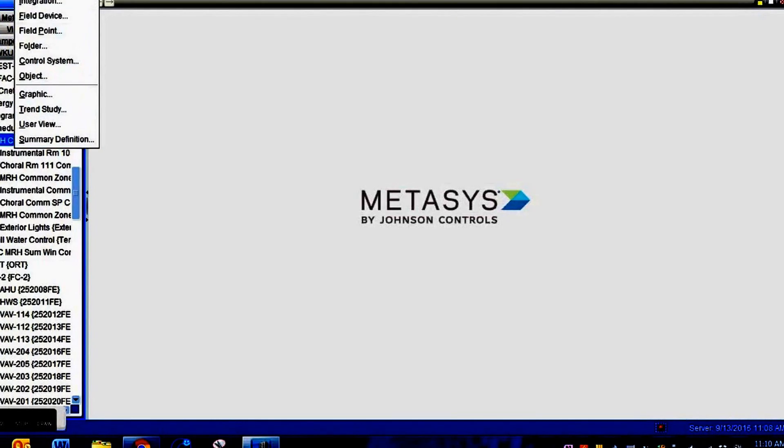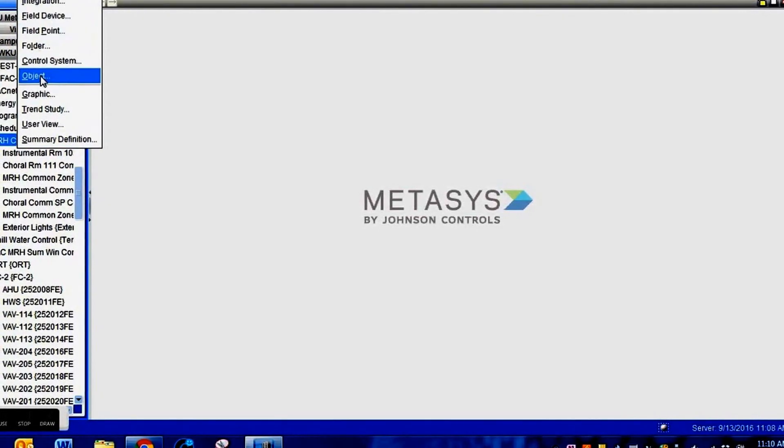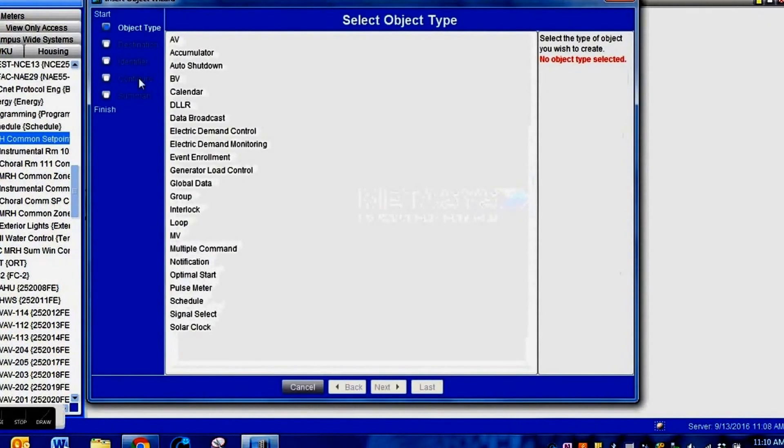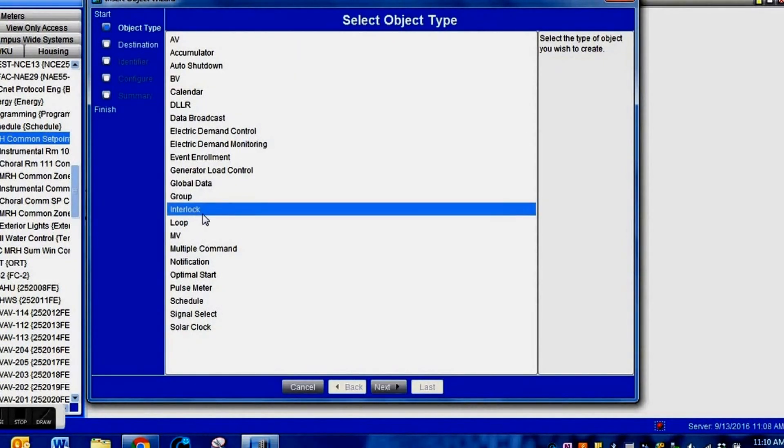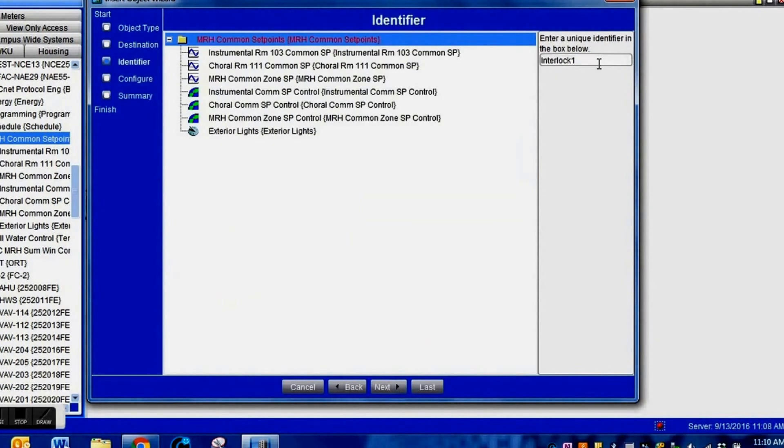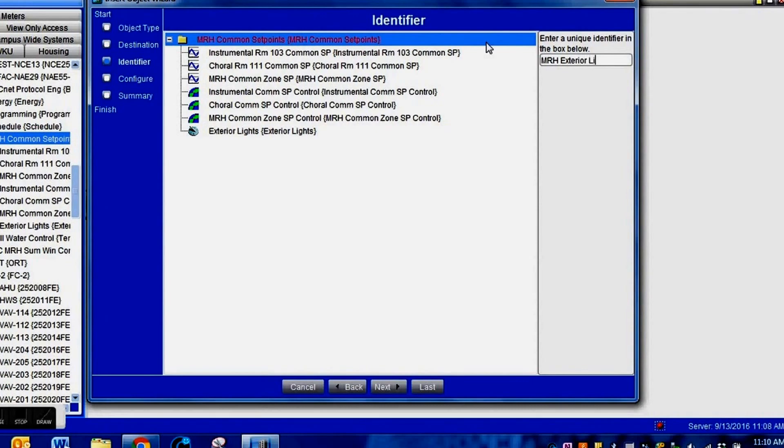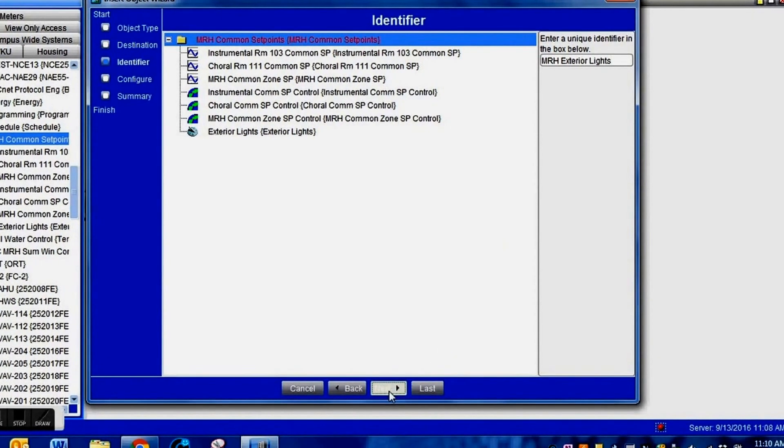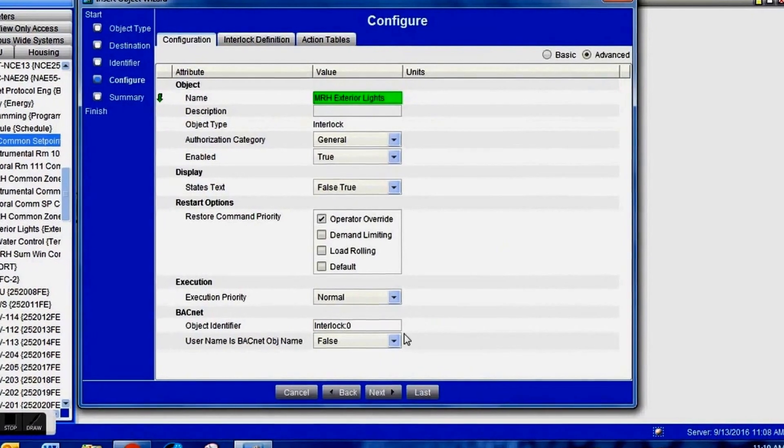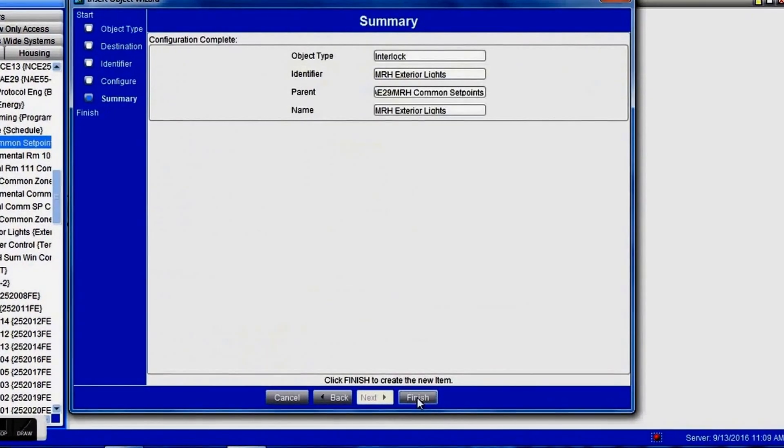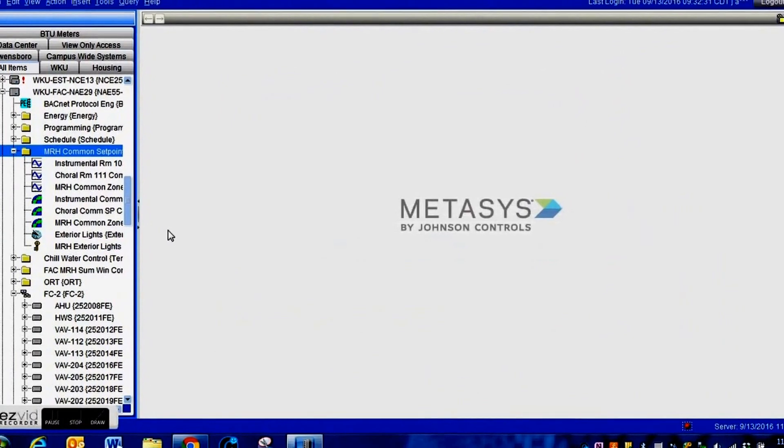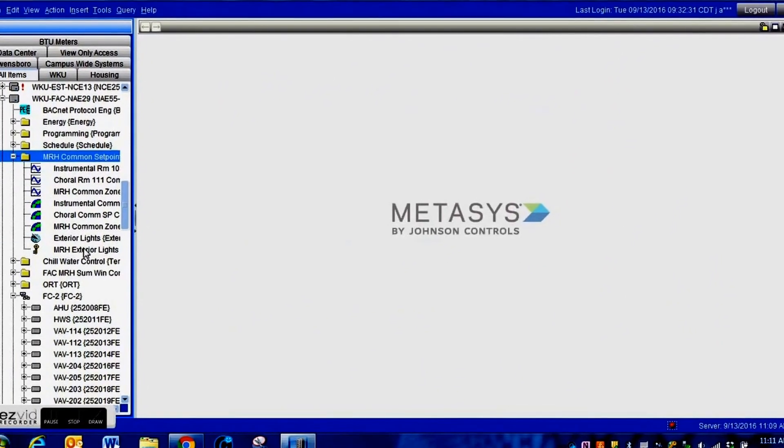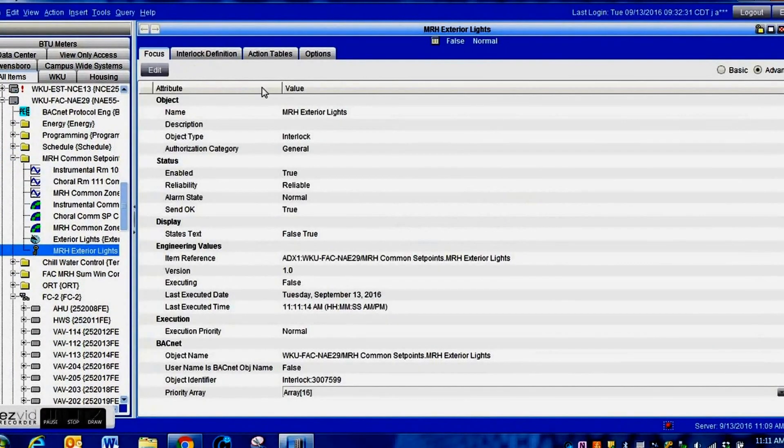The next object we need to create is an interlock. We're going to go up and insert another object and select interlock. We're going to use the interlock to actually change the command point on our controller. Give the interlock a name that is related to the system it is controlling. That's very important and will help you tremendously when you come back for troubleshooting.